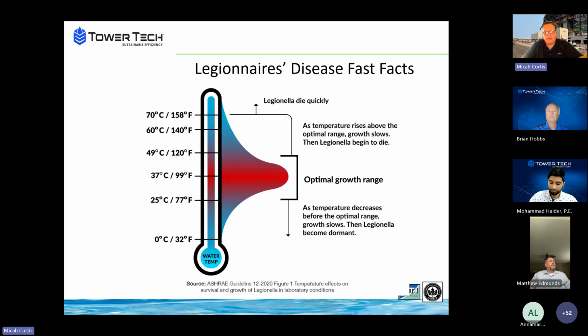So, Mohammed, let's talk about some of the temps that Legionella bacteria starts to grow and proliferate and go crazy. What temperature ranges are we really looking at? Yeah, so the interesting thing about Legionella is that the optimal temperature range, which we consider the sweet spot for growth of the actual bacteria itself, is around 77 degrees Fahrenheit to 120 degrees Fahrenheit. Anything below 77 degrees Fahrenheit, the movement and growth of the bacteria slows down. And anything above 120 degrees Fahrenheit, the bacteria begins to die because of harsh conditions. So those are the temperature ranges where it is known to grow and proliferate.